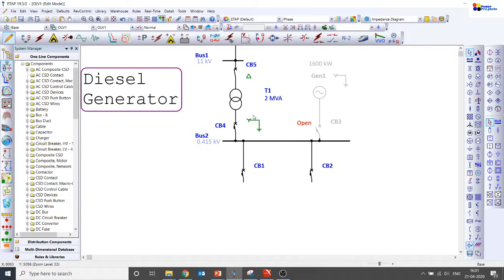Why is this generator on the LV side star? The simple reason is we might have single-phase loads at the LV side, so it has to be star and it should be solidly earthed. Why solidly earthed? Most of the time LV system protection devices are air circuit breakers, molded case circuit breakers, MCBs, and fuses. These don't have any special detection mechanisms for earth faults, so generally the LV system is solidly earthed so that fault current is higher and the fault can be identified by the overcurrent principle.